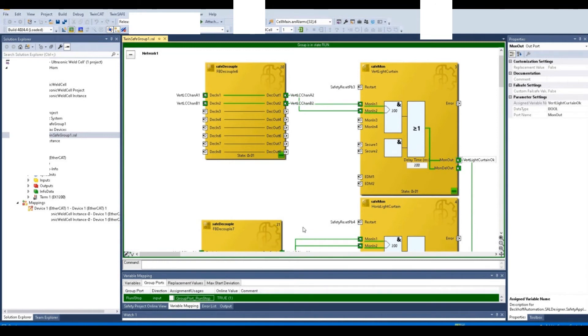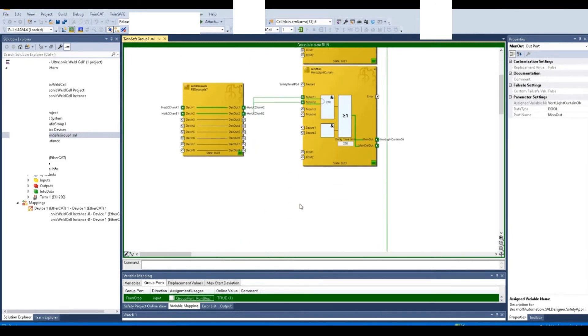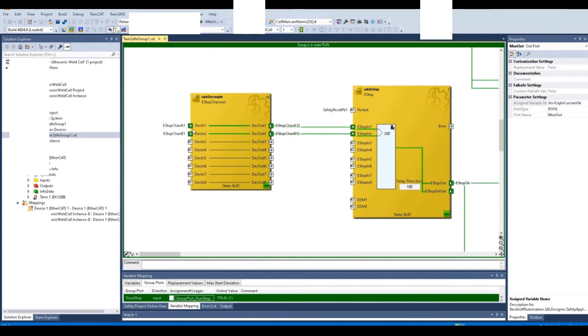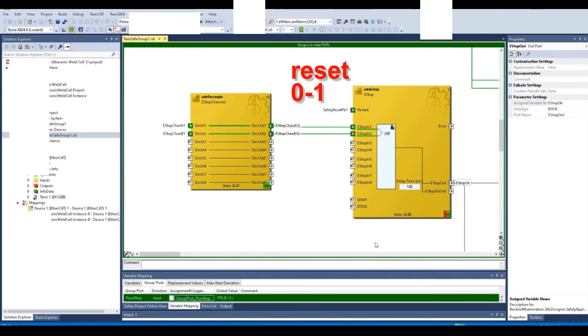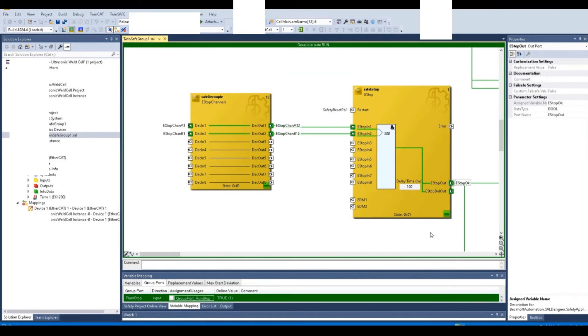This is the light curtain. Now let's go to the e-stop signal. The e-stop has two channels, and this reset button is usually on the control panel. We press the e-stop — the e-stop OK goes off. Without the reset signal it will stay off, even if we release the e-stop button. Now we turn on the reset — we can see the status go from on to off again, so the e-stop OK will recover.